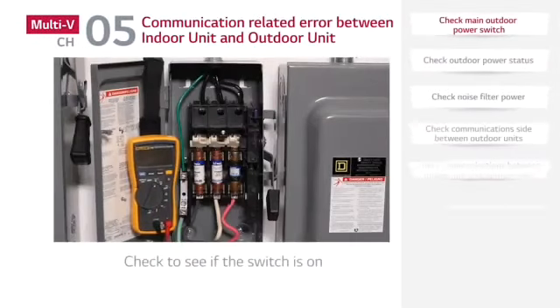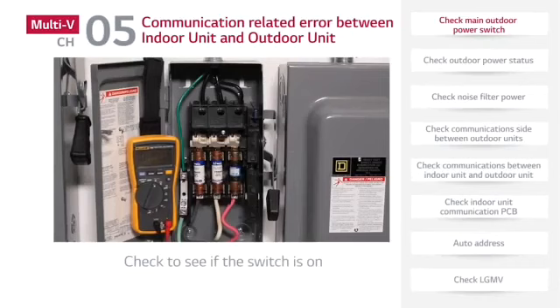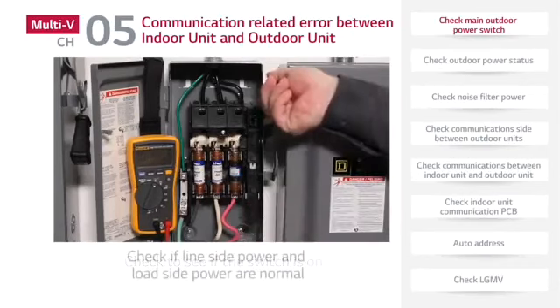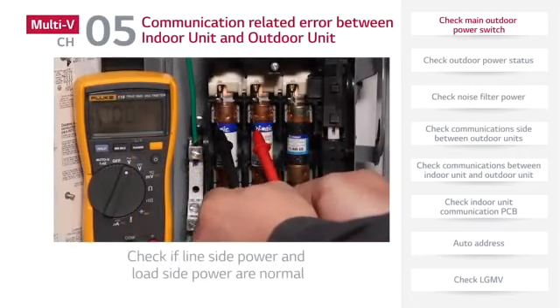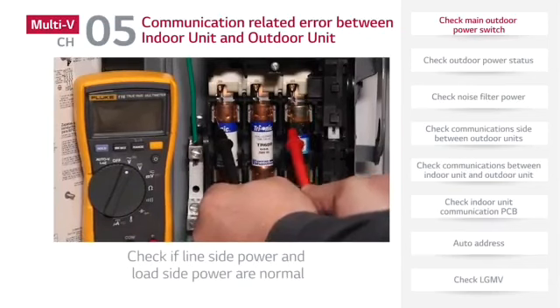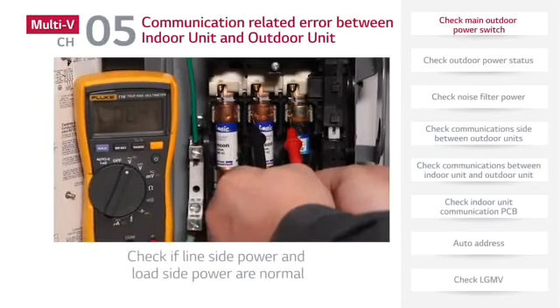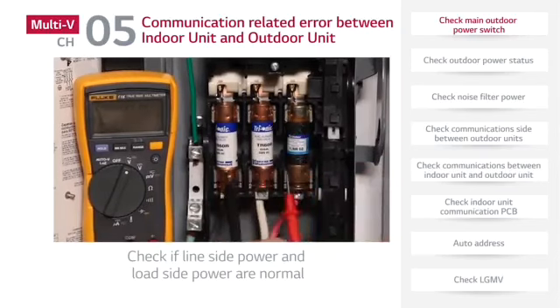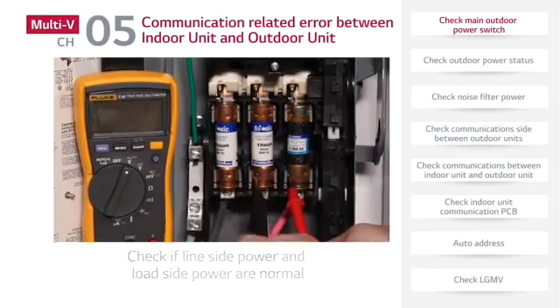When a CH05 error occurs, we must first check the outdoor unit main disconnect power. Check to see if the switch is on. Then check if line side power and load side power are normal. First, check the line side voltage between phases. Next, measure the load side voltage between phases. Voltage between phases should not vary by more than 2%.